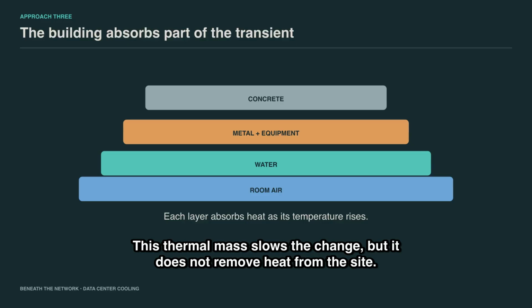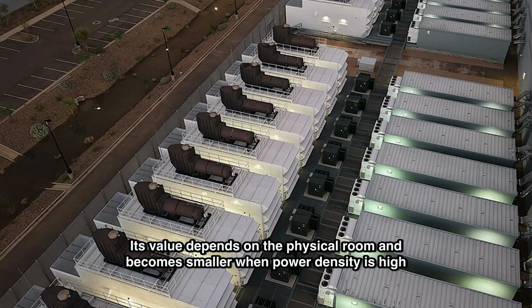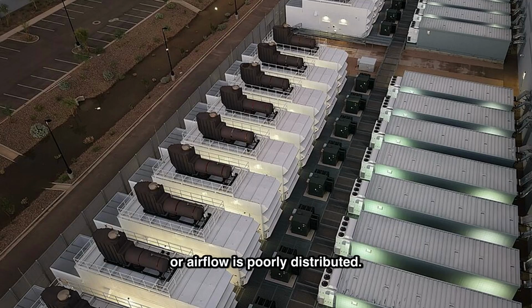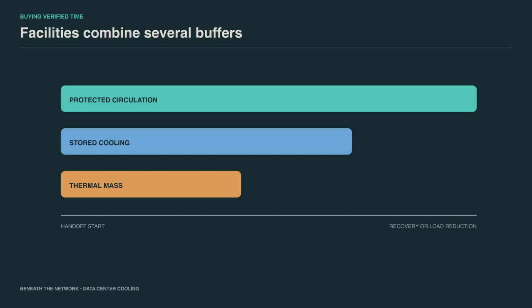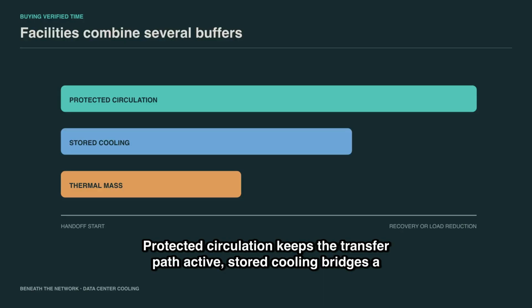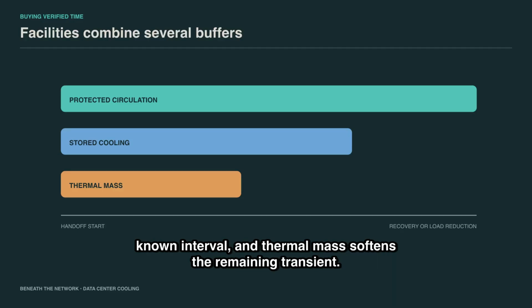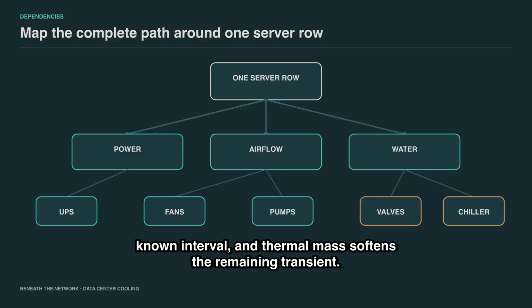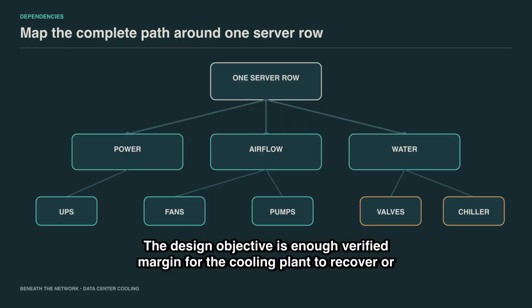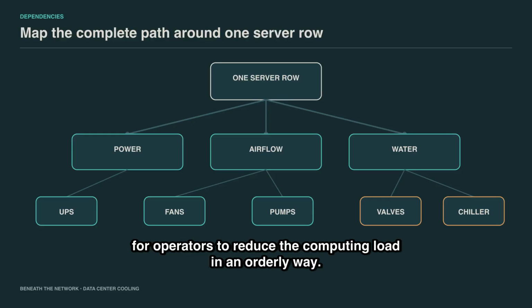This thermal mass slows the change, but it does not remove heat from the site. Its value depends on the physical room and becomes smaller when power density is high or airflow is poorly distributed. These measures are often combined. Protected circulation keeps the transfer path active, stored cooling bridges a known interval, and thermal mass softens the remaining transient. The design objective is enough verified margin for the cooling plant to recover or for operators to reduce the computing load in an orderly way.